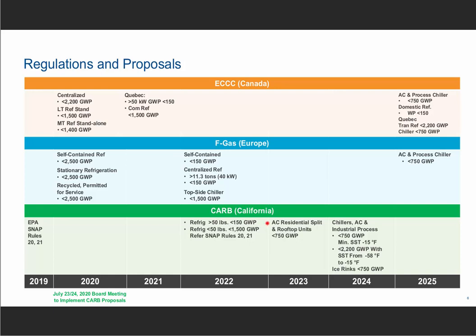Now, from an air conditioning perspective, residential split and rooftop units, by 2023, the GWP limit will be less than 750. And if we move out to 2024, chillers, air conditioning, industrial process, anything above minus 15 Fahrenheit SST falls within the less than 750 GWP range. And if you're between minus 58 Fahrenheit and minus 15, then the GWP limit is a little bit higher. So those are some of the California regs and other parts of the region.